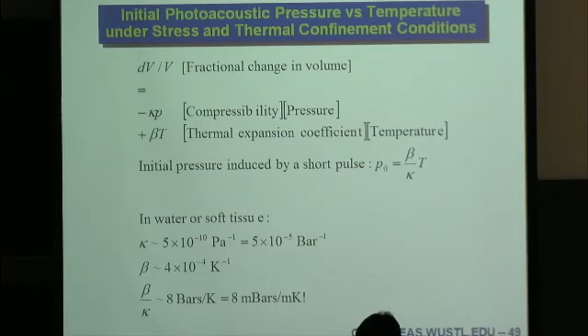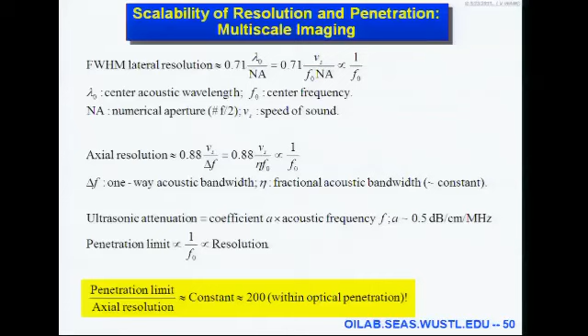Another constant, another conversion. Look at the penetration versus axial resolution in this modality. The resolution in both the lateral and axial direction is inversely proportional to the ultrasound frequency, but ultrasound attenuation is proportional to the frequency, so the penetration is inversely proportional to the frequency. But the ratio is relatively independent of the ultrasound frequency, and we don't really control that ratio very well. That's all material property dependent. And it turned out that constant is 200. That means we can provide you 200 pixels to work with. If that constant is 2 instead, we'll only give you 2 pixels. You'll hate our images. So now we have high resolution images because of this constant.